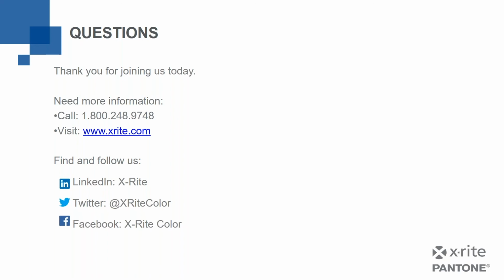Because when you send it to X-Rite, we're putting it into a very tightly controlled environment and testing it there. And it could perform well there and not as well when we put it in your environment, because we're sitting at 72 degrees and 51% humidity, and you're going to go use it in 84 degrees and 80% humidity, and that's suddenly going to make it behave differently. So profiling is about making sure your instrument works well where you use it.